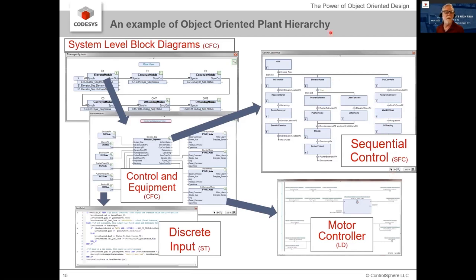Here's another example — a material handling system with an elevator module, three conveyor modules, and two offloading modules. Eventually you get down to the control and equipment diagram, where discrete inputs such as proximity switches are on the left, their outputs feed your control block, and the control block's outputs feed your output equipment — in this case, motors. IEC 61131 and CODESYS give you lots of languages so you can use the best language for the job. CFC is best for block-based design. Sequential function chart is best for state machines with discrete feedback. Ladder logic is good for simple combinatorial logic. Structured text covers basically everything else.